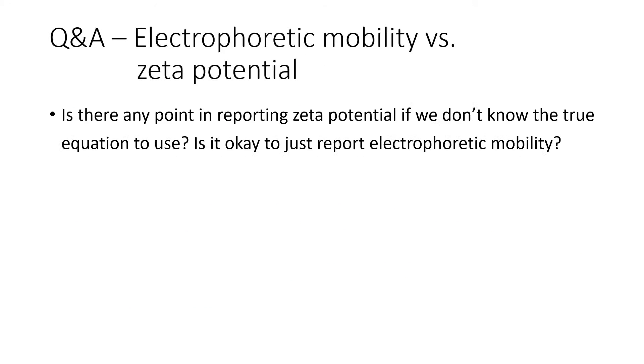Question: is there any point in reporting zeta potential if we don't know the true equation to use? Is it okay to just report electrophoretic mobility? Firstly, the instrument measures electrophoretic mobility and anything else it reports — zeta potential — is derived from it. So you aren't going to lose anything by doing so, and it is more appropriate to use it as raw data than zeta potential, because of all the problems I've described about calculating zeta potential from the mobility.